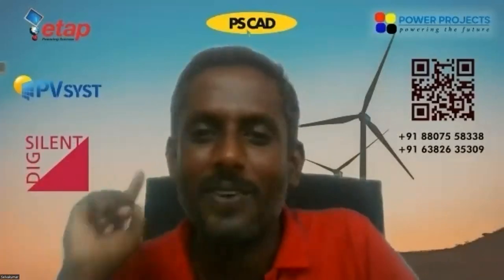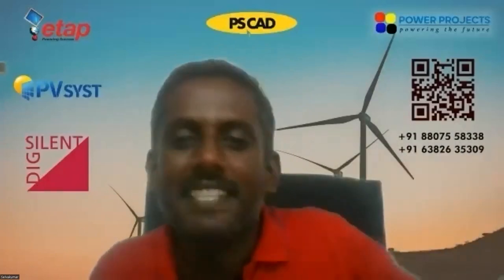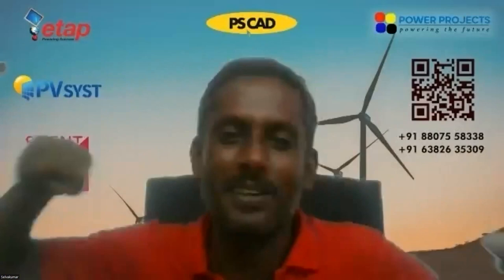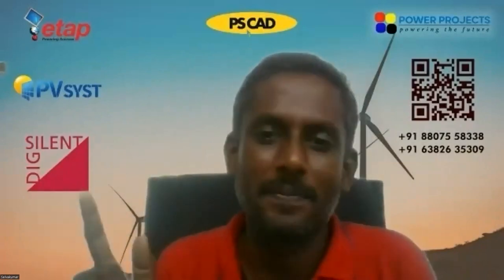I have seen quite a lot of arc flash reports without relay settings or protection settings, still claiming that it is safe to work, or that you have to wear PPE, etc. Try to understand this. If you are not doing a short circuit study to understand the short circuit current, and you do not have proper protection coordination settings, whatever arc flash study you are doing is useless.